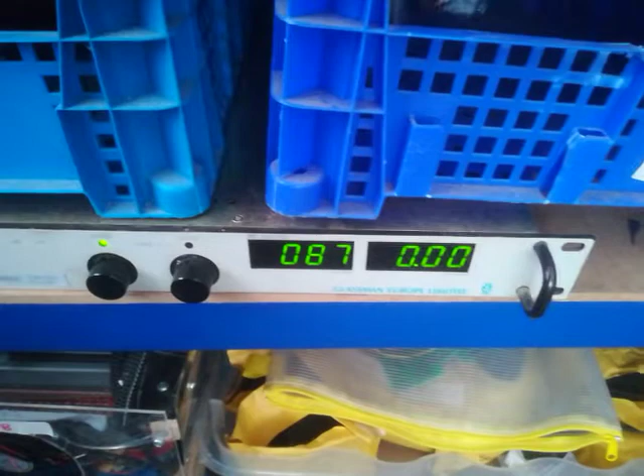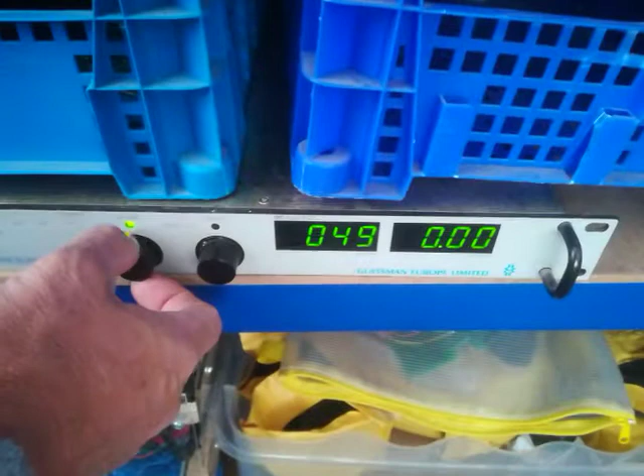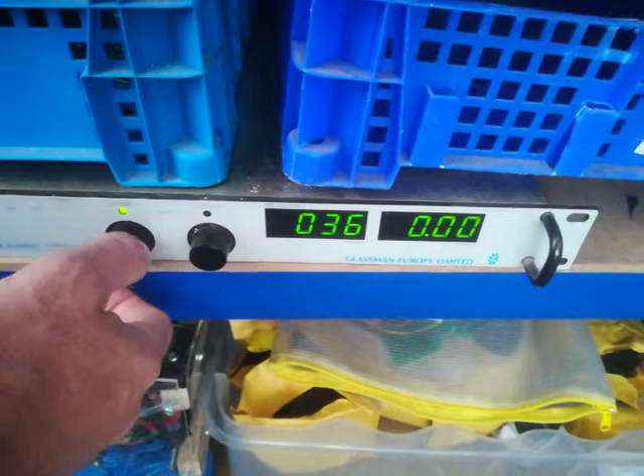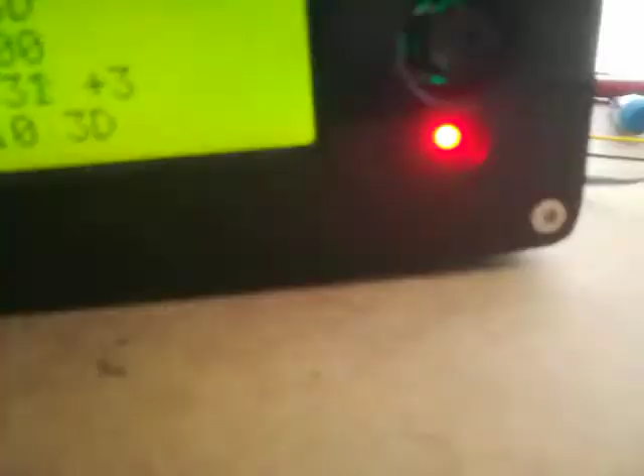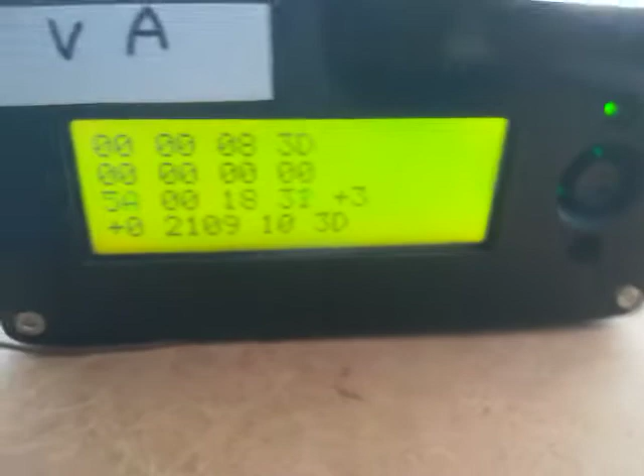I'll drop that back down again for safety, I don't want to be grabbing hold of it later. I'm using 32 volts as a test voltage, adjusted to a very low current, because that's safer. So it's on 32, and here we are, it just says 31, occasionally flashing to 32. So it's accurate, probably to about a volt, which is pretty good.